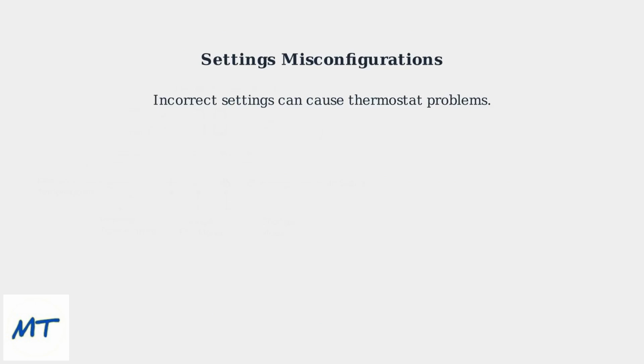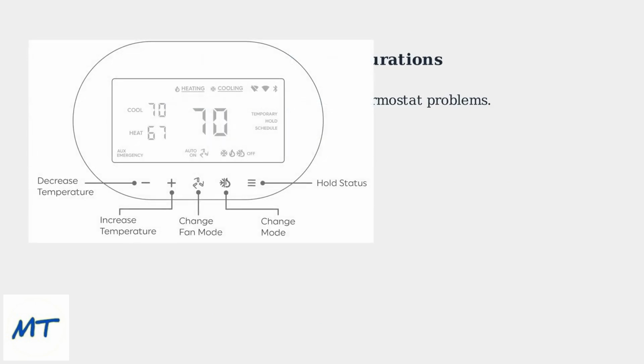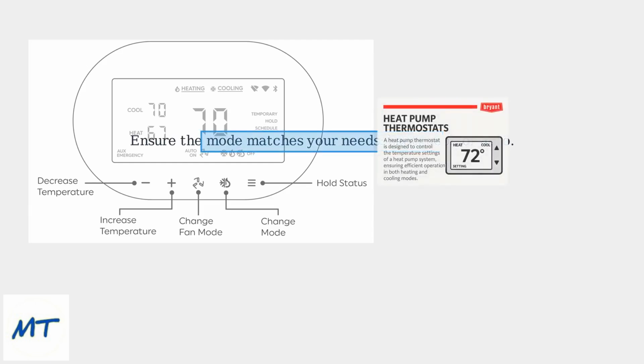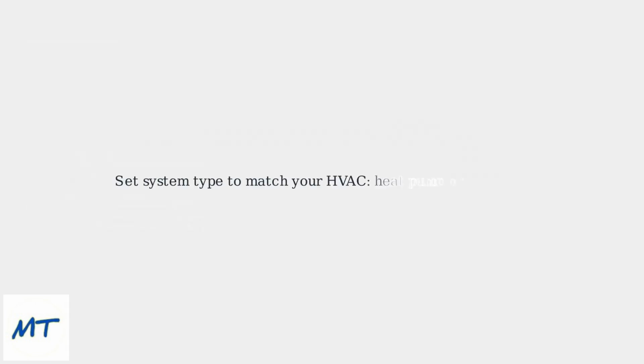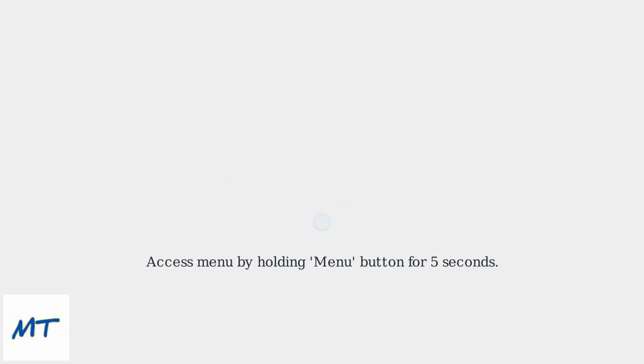Incorrect settings can also cause problems. Make sure the thermostat is set to the correct mode, heat, cool, or auto, and that the system type matches your HVAC unit, whether it's a heat pump or standard system. The mode controls whether the thermostat activates heating, cooling, or automatically switches between them based on temperature. The system type must align with your HVAC setup. Choose heat pump for systems that both heat and cool using one unit, or standard for separate heating and cooling systems. To adjust these settings, hold the menu button for 5 seconds to enter the configuration menu, then navigate to make the appropriate changes to match your HVAC specifications.